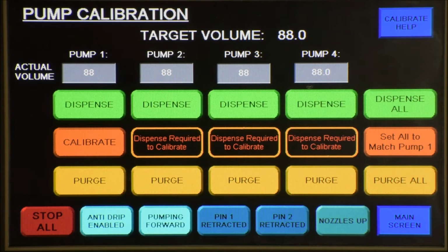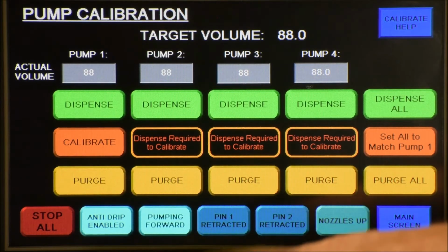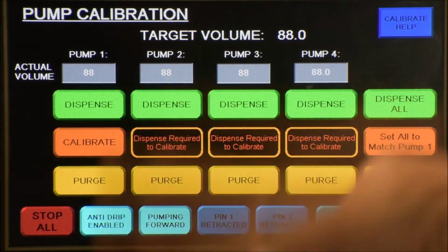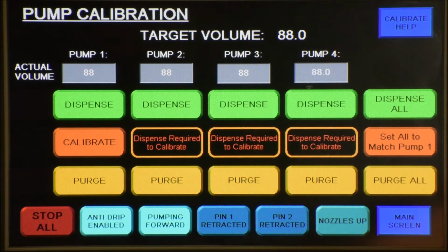Along the bottom on this screen, there's a few key settings. Anti-drip: what that's doing is that after it runs its fill volume, it runs the pump in reverse a certain number of steps that's programmable in the recipe to suck up any drips from that nozzle. So your choice on if you want to run it, you can turn it on or off. If you calibrate with it on, it will include those steps in the calibration.